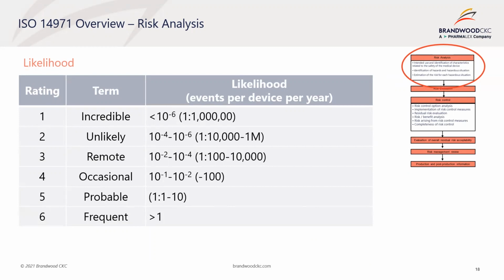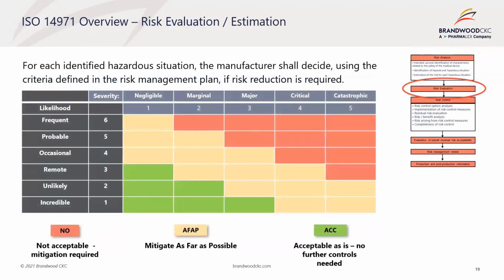Several approaches are commonly employed to estimate likelihood, such as use of historical design and development data, prediction of probabilities using analytical or simulation techniques, use of experimental data, reliability estimates, production, post-production information, or use of expert judgment. ISO 14971 requires that the manufacturer perform a risk estimate of each risk. For each identified hazardous situation, the manufacturer shall decide, using the criteria defined in the risk management plan, if risk reduction is required.